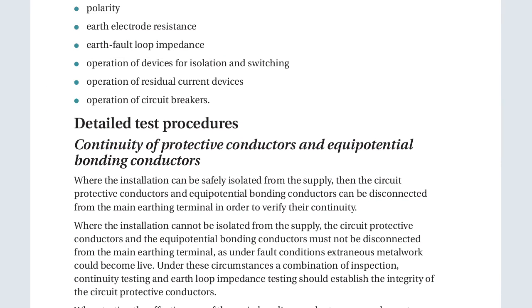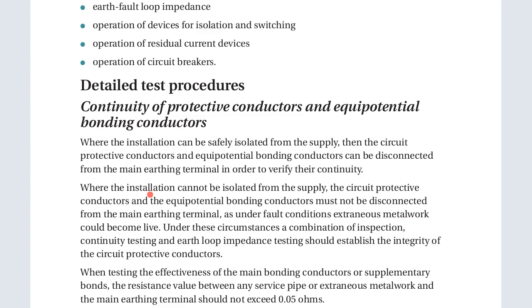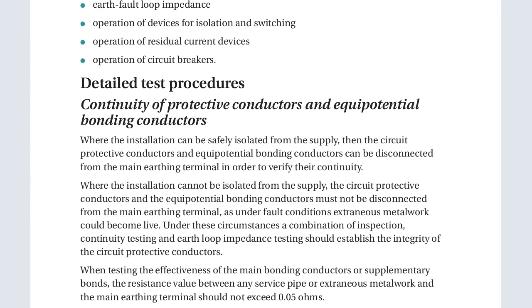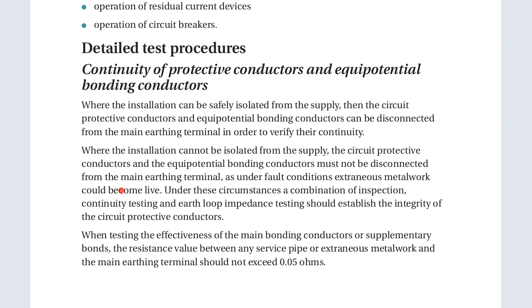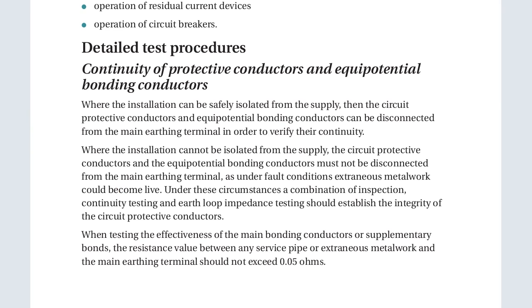So we detail the test procedures that are needed. These are the types of tests that we need to carry out. These tests are very important. You will even need to apply them when you apply for a license. Let's say you want to apply for a technician license at the ERC. You need to know these tests because they are among the basic tests examined during the licensing. So we have one called the continuity of protective conductors and equipotential bonding conductors. In short, it is normally called the continuity test.